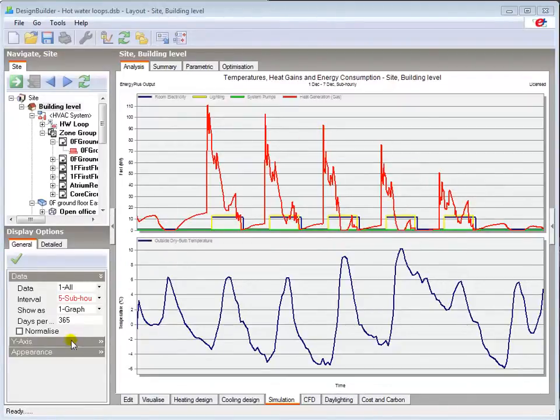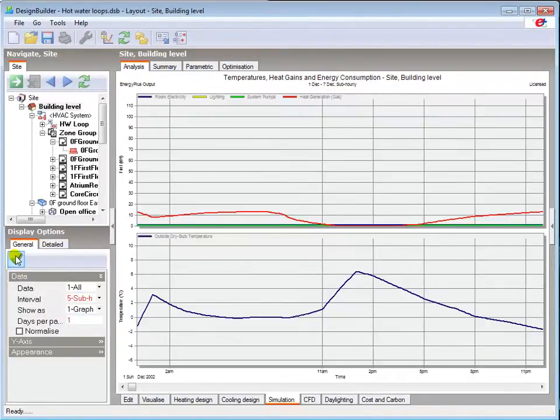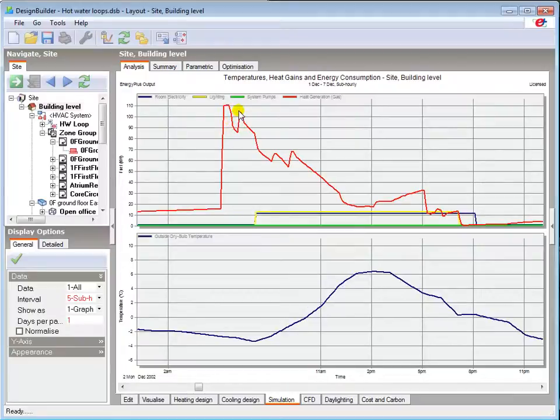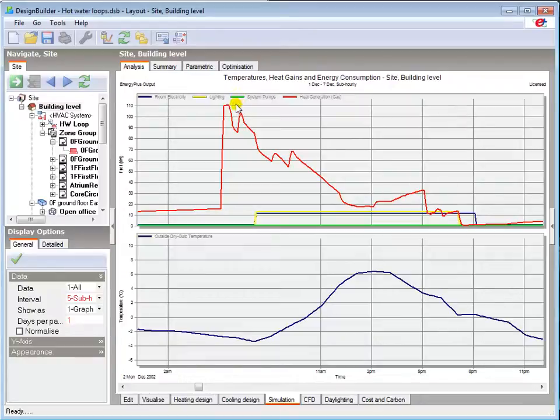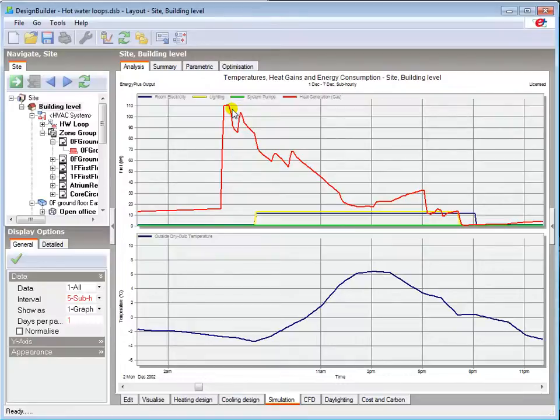Going to the single day view and navigating to Monday shows that the heating fuel consumption peaks or flatlines for a short time just prior to occupancy. This is the kind of detail that may not be evident using less time steps. The flatline means that the plant is operating at full capacity, which, given the boiler efficiency of 89%, would equate to a heat gain to the building of around 100 kW.